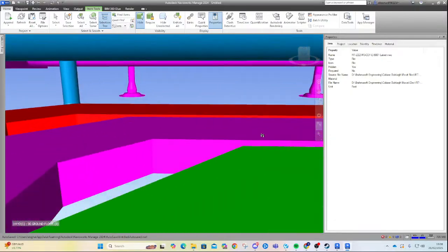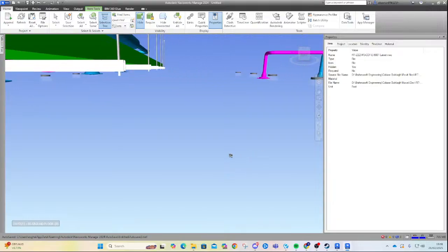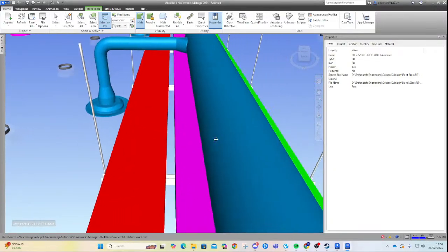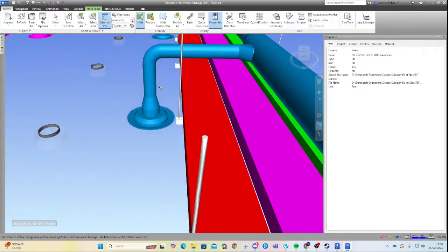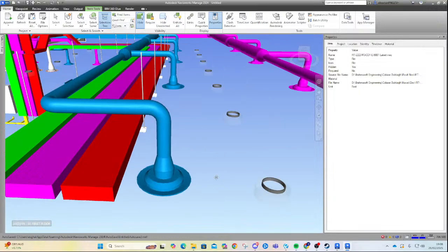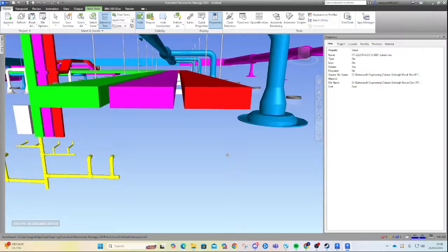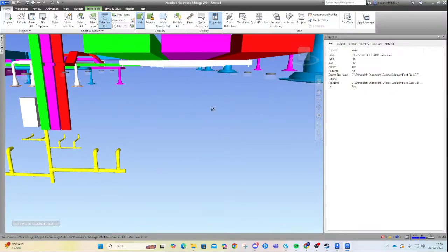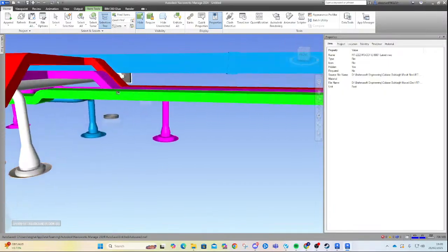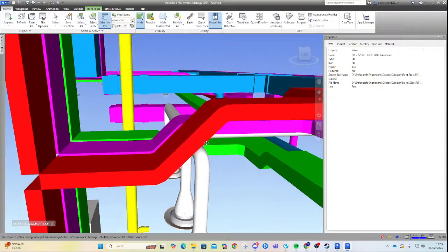So we're keeping all these nice and straight, and the reason we do that is so one bracket will span the width of the cable trays. And we can also add brackets in for these here as well, but it's the same process. So if you can add brackets onto the cable trays, you can add them onto the ductwork. You just want to keep them nice and level like that for brackets. So when we come up here, we come out at one level. So if we need to bracket these somewhere, we can.